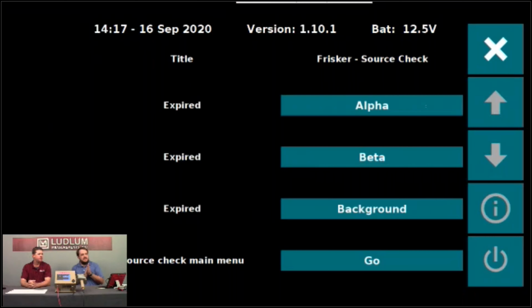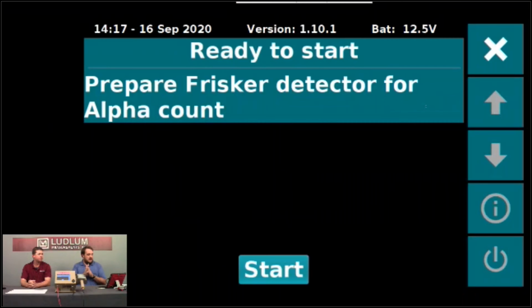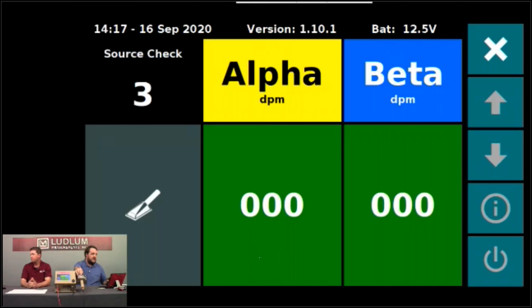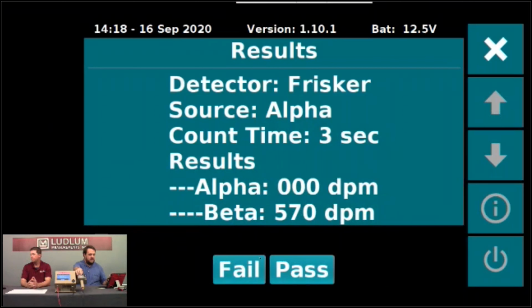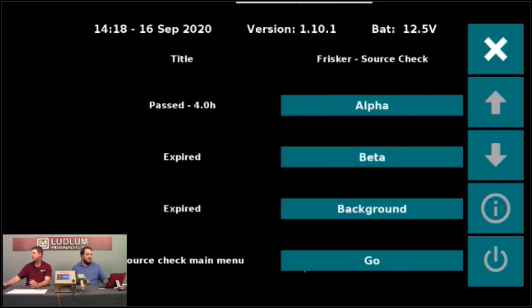So if I click the alpha, the unit will ask us to apply a source to the instrument, or to the detector. And once we've done that, you'll click the start button and it'll automatically start the count and then give you the results. So it was a 3-second count and we have 570 DPM for beta and 0 alpha. So I'm going to say that was a pass.